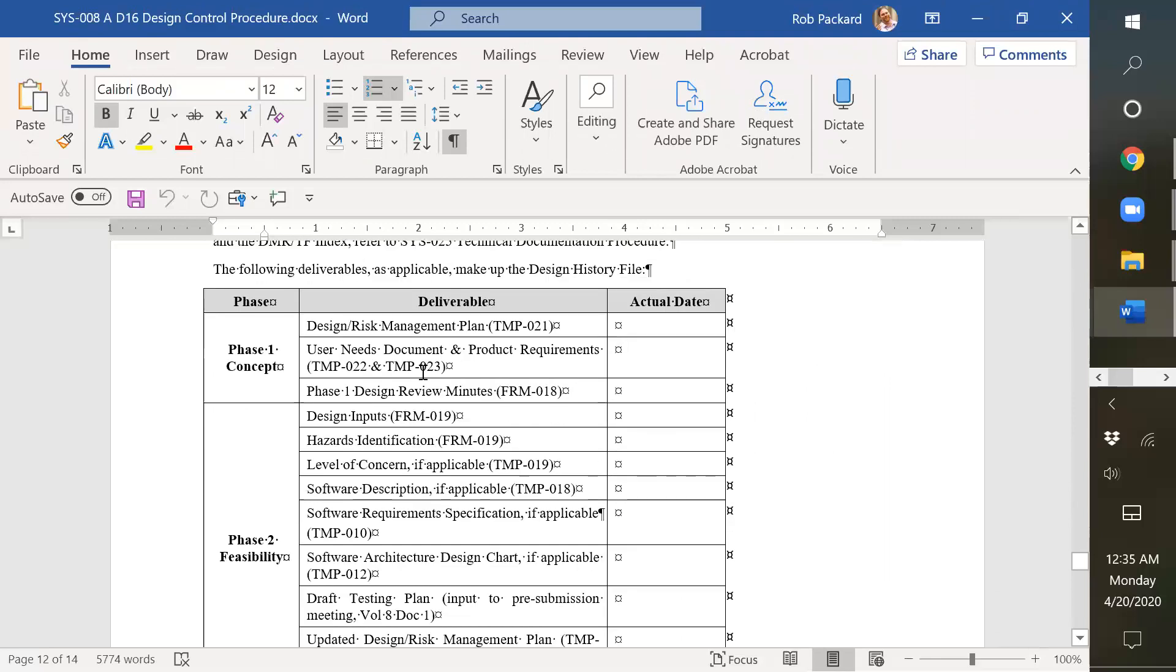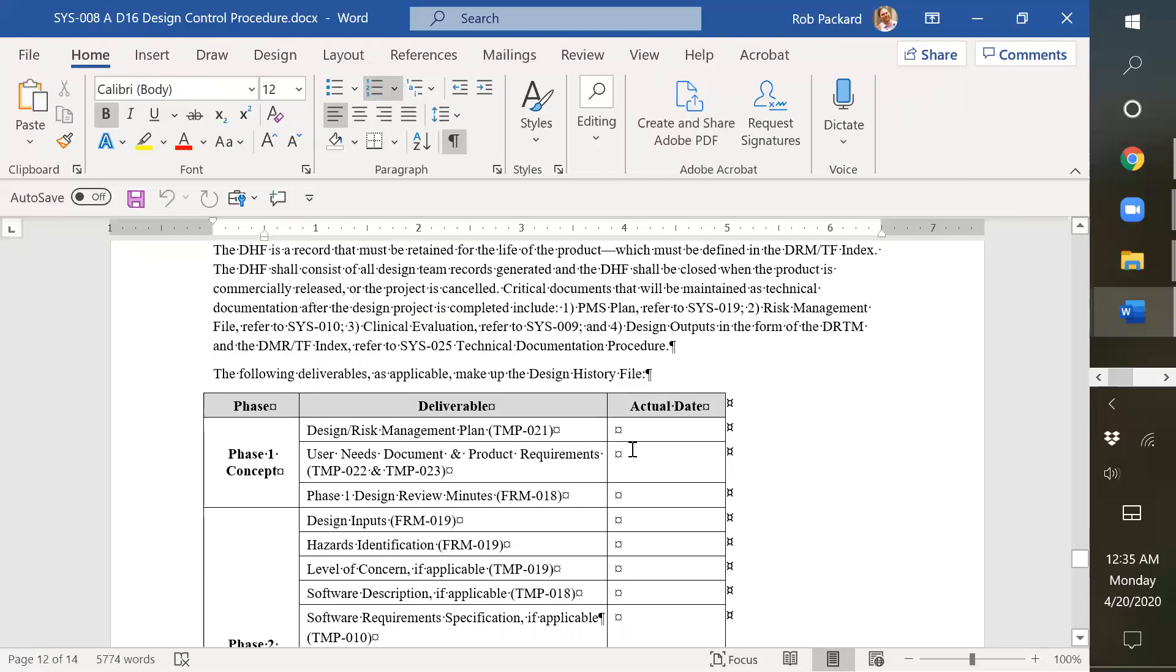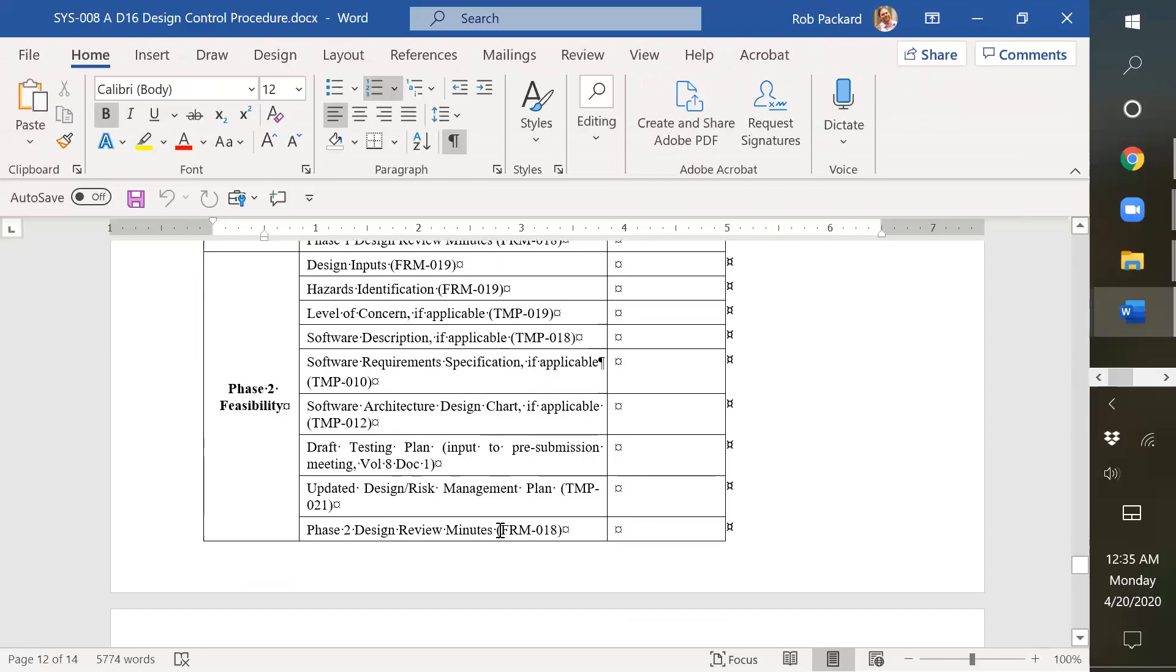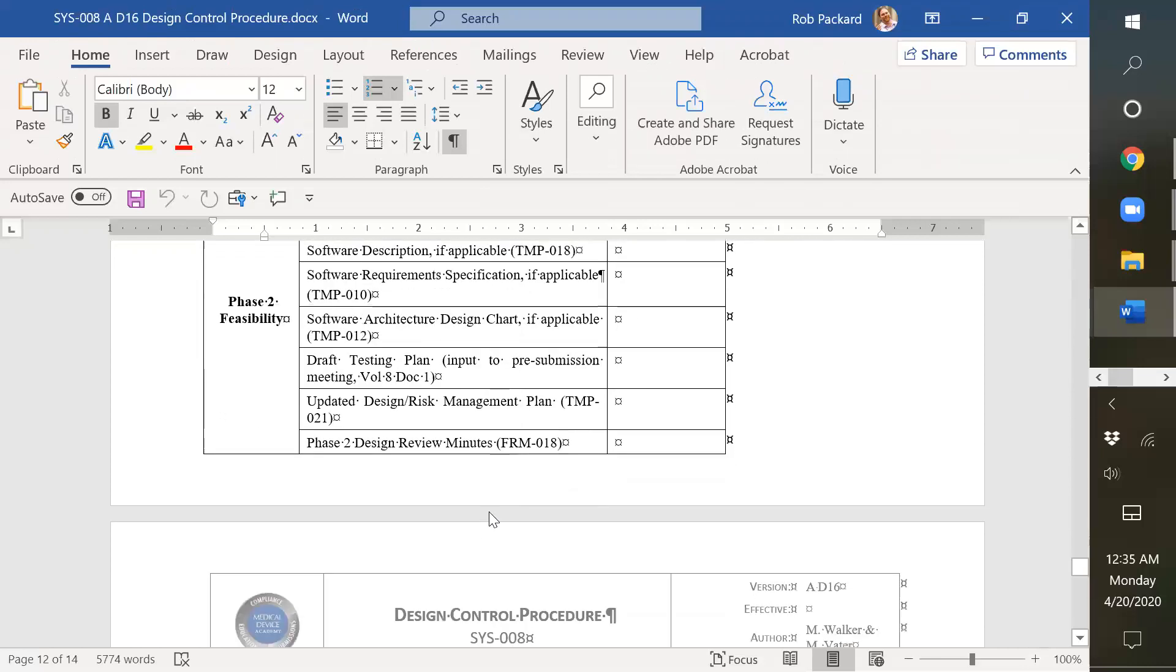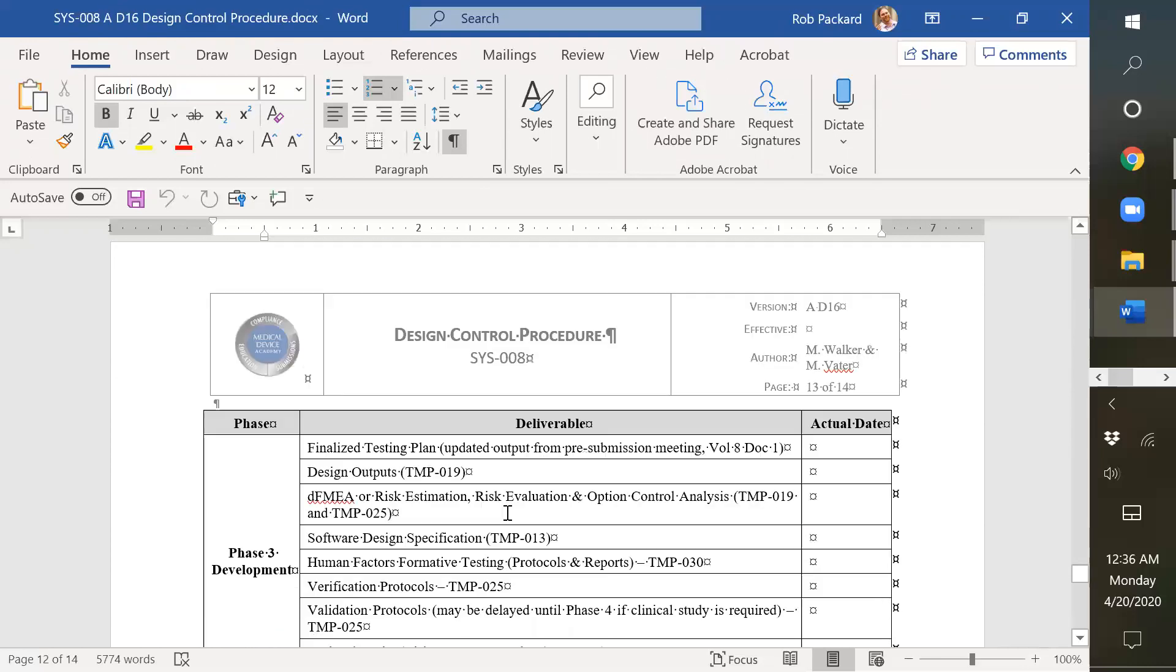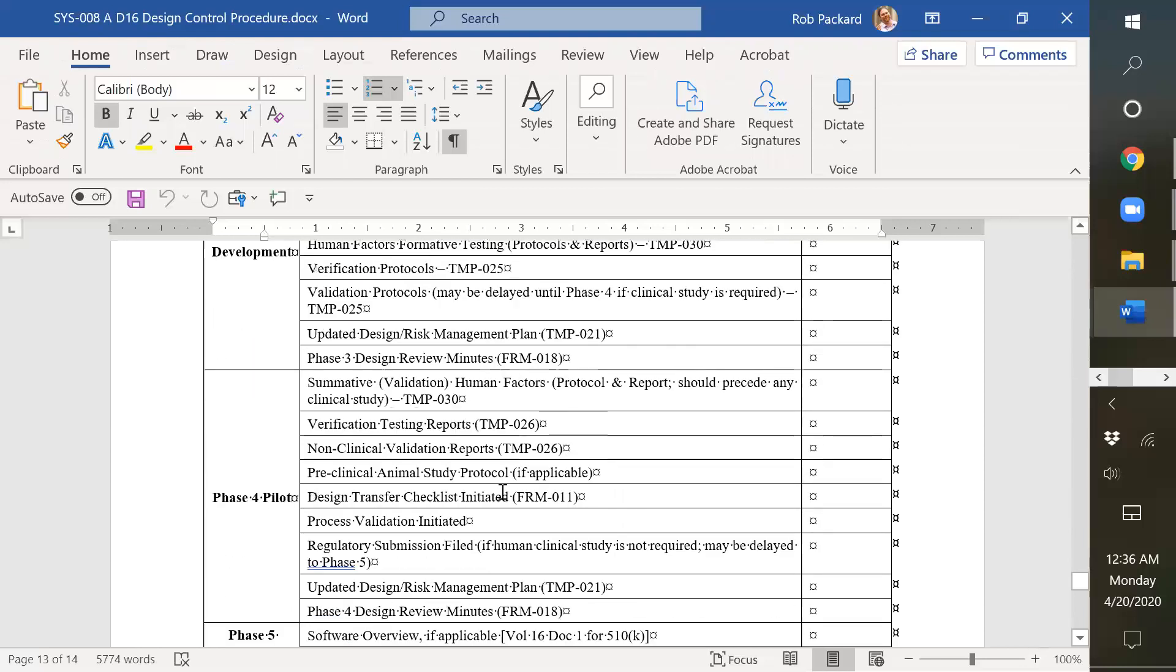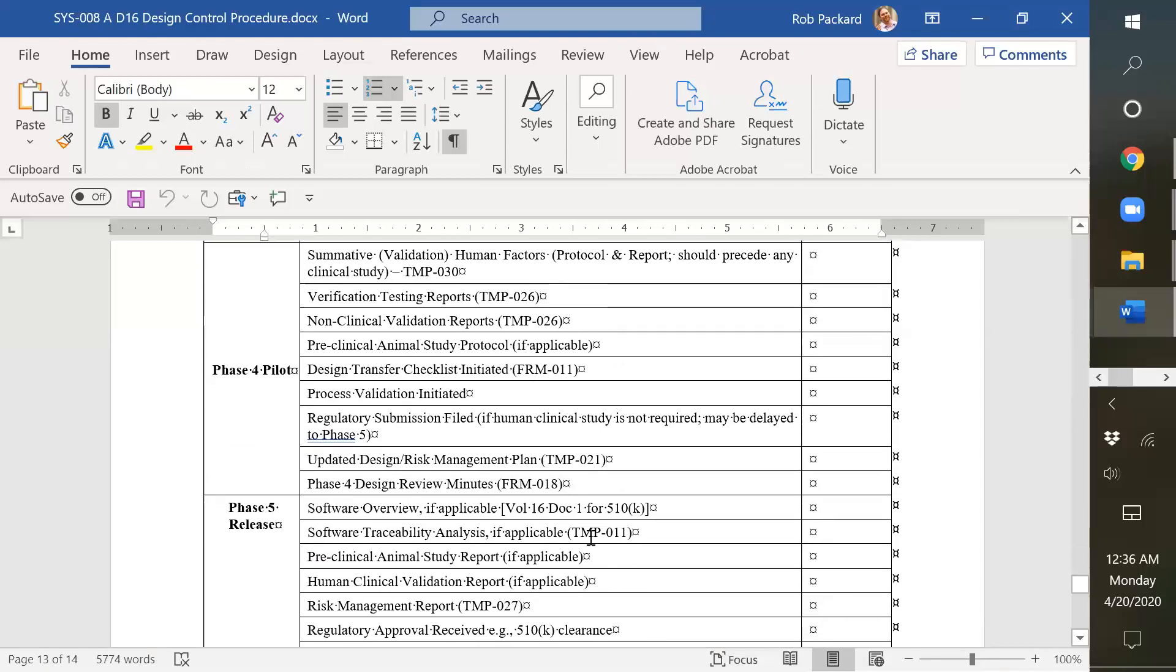And here are all the different records that you would put in a design history file, organized by phase. And this is very much a copy from what's also in the design plan. So for each part, we've just recently added all the cross-references to the different templates to help people keep track of where which documents go and which sections.